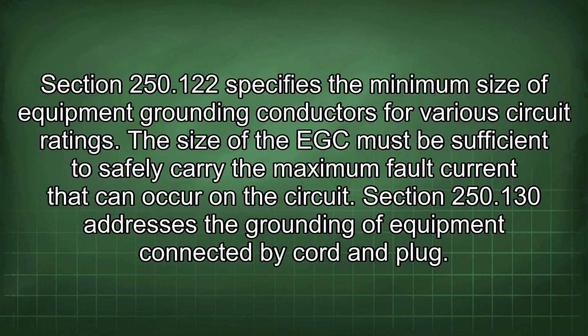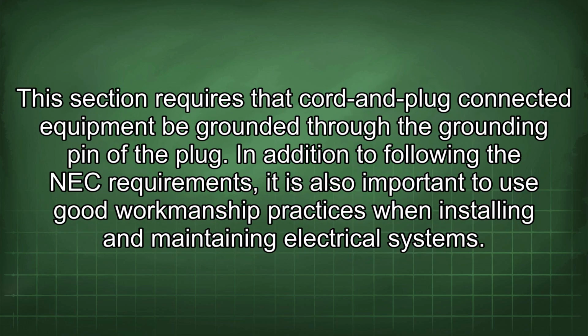Section 250.122 specifies the minimum size of equipment grounding conductors for various circuit ratings. The size of the EGC must be sufficient to safely carry the maximum fault current that can occur on the circuit. Section 250.130 addresses the grounding of equipment connected by cord and plug. This section requires that cord and plug connected equipment be grounded through the grounding pin of the plug.